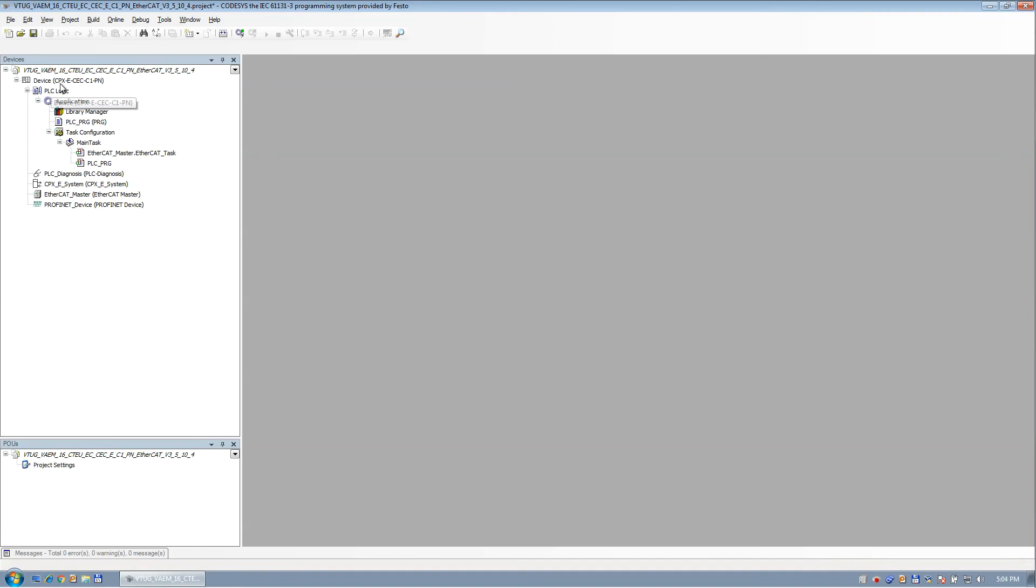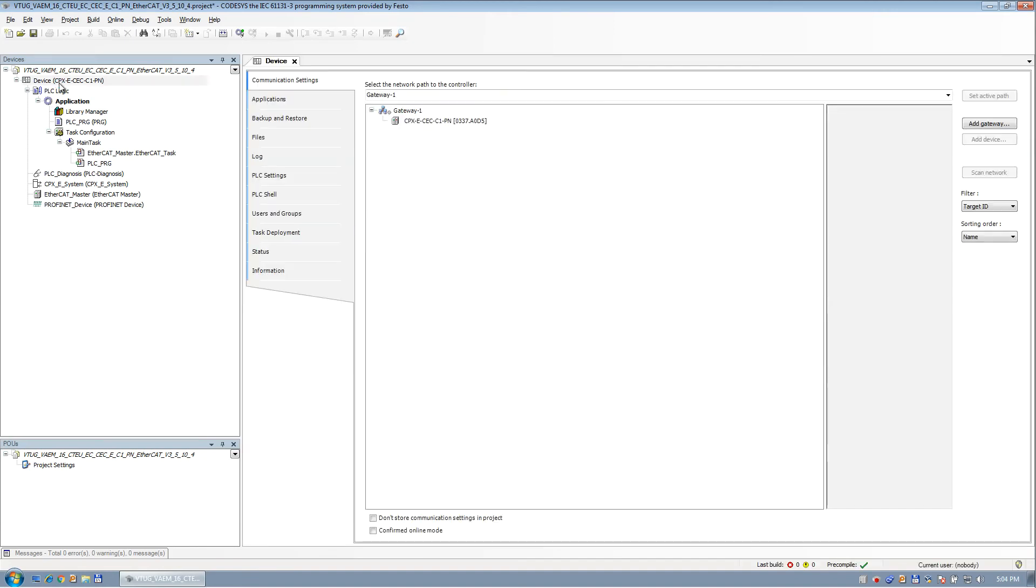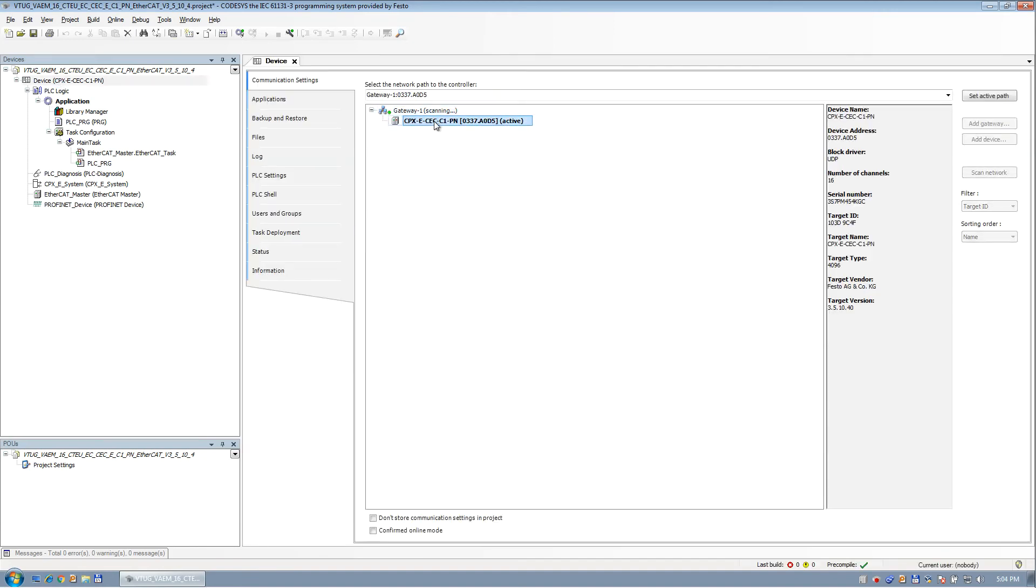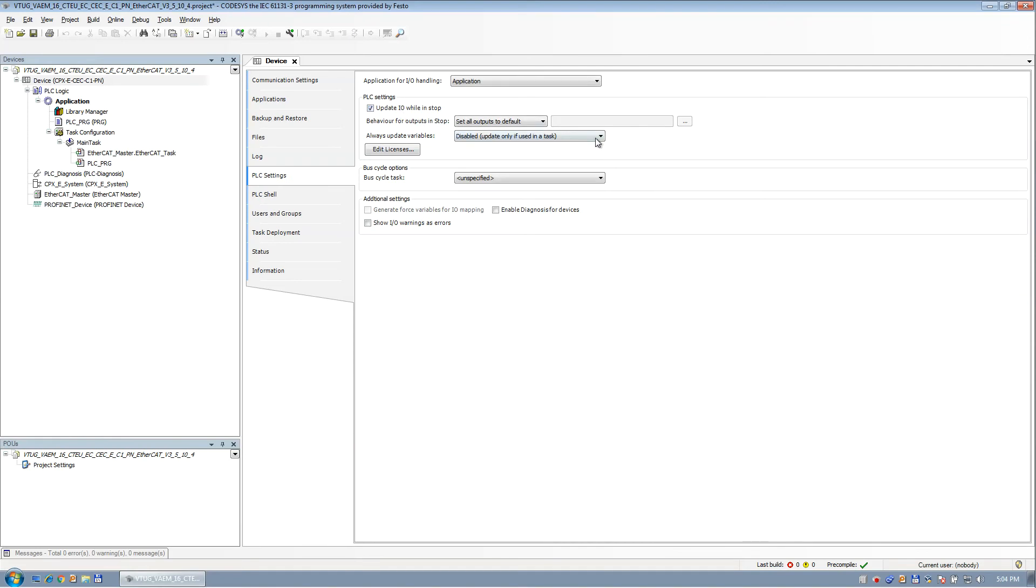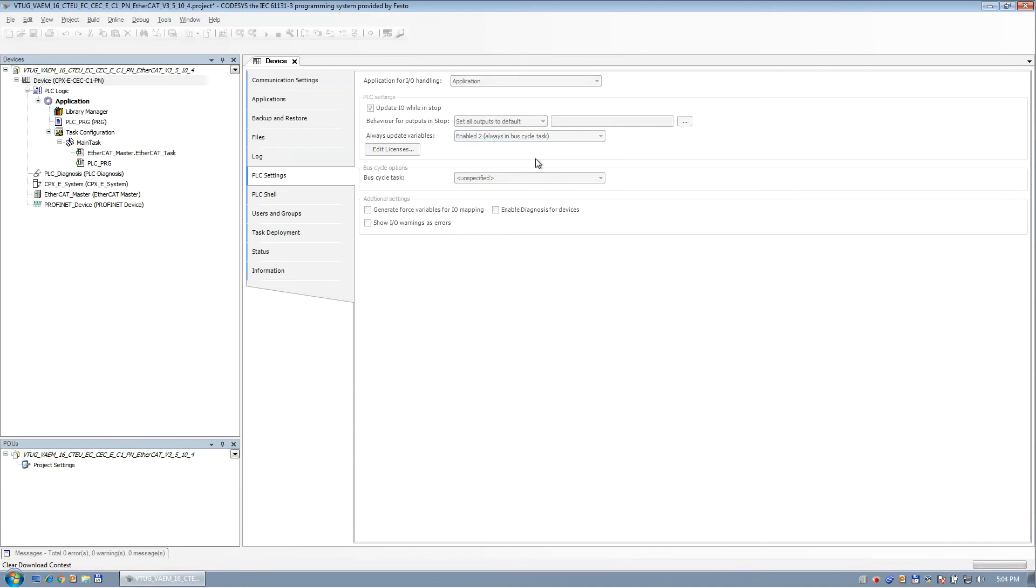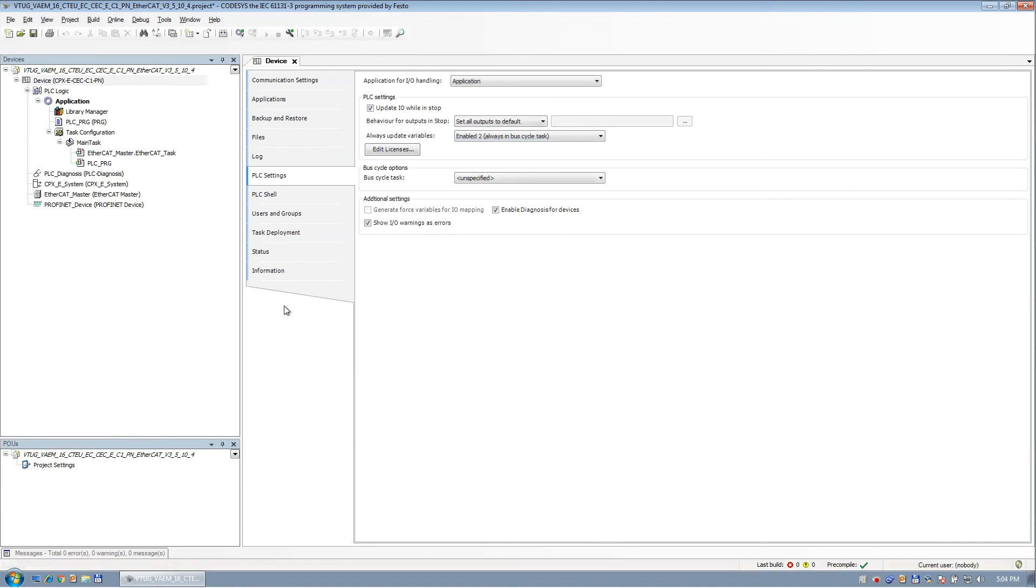A couple of first things I always do - double-click on the device, scan for the PLC, double-click it, or set active path. So now we have that in our project. Next thing I always do, I like to have update I.O. and stop. It's a little bit like TwinCAT back off, so that the I.O. is always scanning. And I always enable the I.O. so it's in the bus scan. These as well, and main task as the bus cycle task. That's very important.